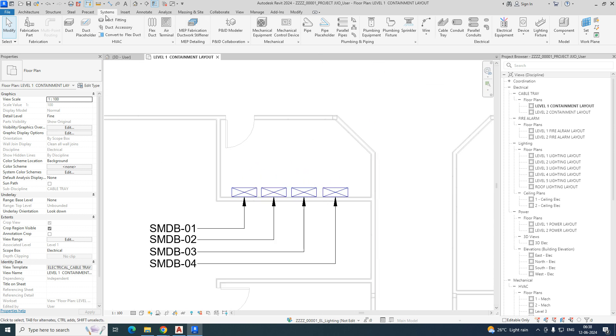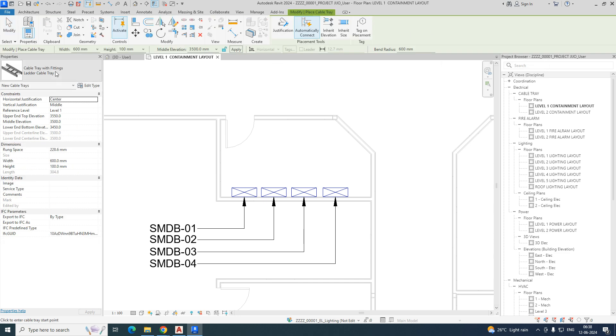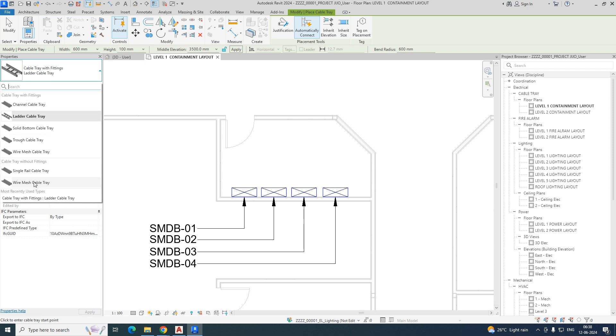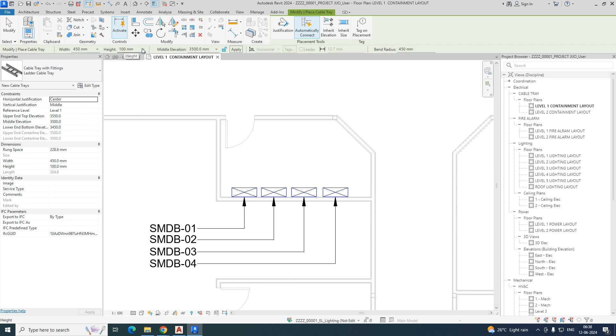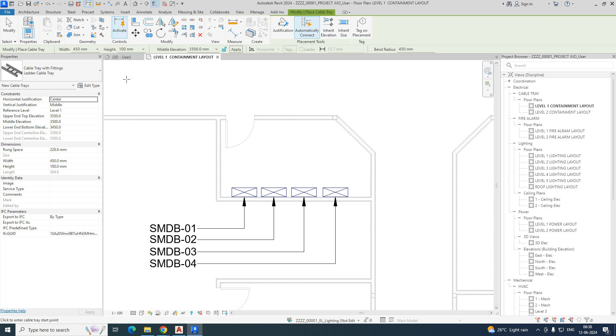Go to System, then choose Cable Tray. You can get different types of cable tray from here. I am choosing Cable Tray Ladder, then select that one. You need to give the size of the cable ladder — for example, I'm choosing 450mm cable tray ladder. Here you can give the cable tray height, like 50mm or 100mm. I am choosing 100mm.